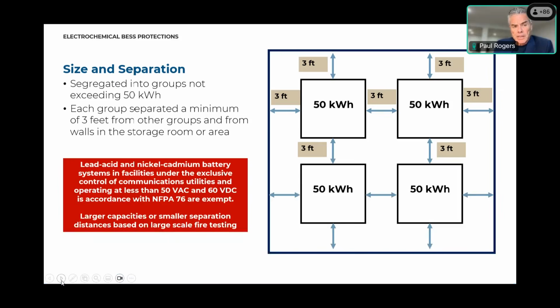Can we go higher than that number? The answer is yes, but if you're going to go higher, you have to do large-scale fire testing to make sure you can't have a failure that propagates to the adjoining ones. Can you go closer to the wall? Sure, and that's also based on large-scale fire testing. So there is a way out, as long as you do the proper testing and it's approved by the local jurisdiction.